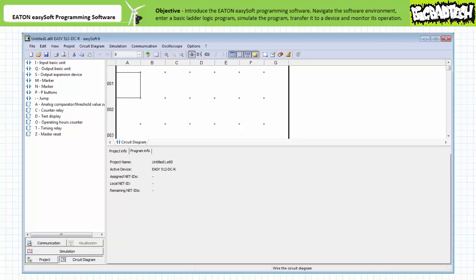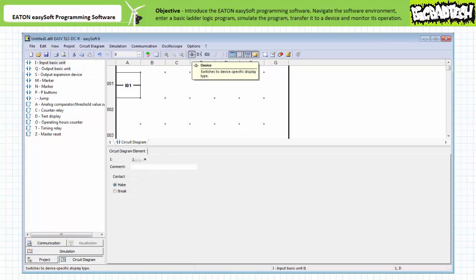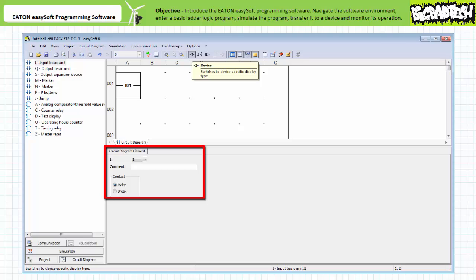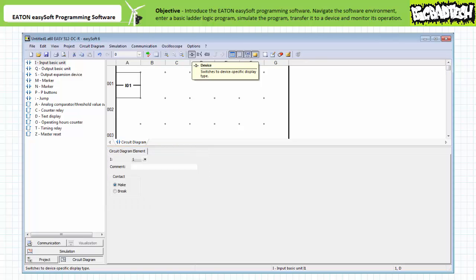To add a contact or coil to the program, drag and drop the appropriate selection from the left menu onto the workspace. Here I've dragged an input basic unit onto rung 1, column A. The default operand number is 1 and the default instruction is make. Note the circuit diagram element tab allows a user to select the operand number, enter comments, and toggle between make or break instructions. Note the comment field allows a user to enter device-specific information for later referencing or troubleshooting purposes. If you make a mistake, you can always click on the element to select it and change the operand number or delete it entirely. Within the easySoft programming software environment, contacts are designated using the default device format displayed alphanumerically. The default device format symbolizes a make instruction without an overbar, whereas a break instruction is designated using an overbar, signifying negation.